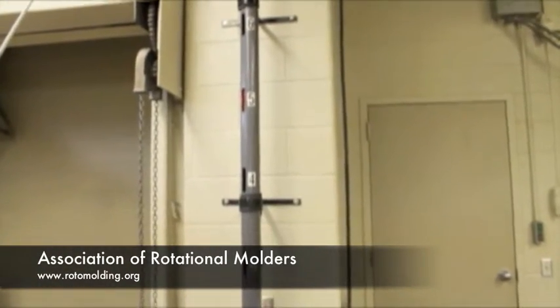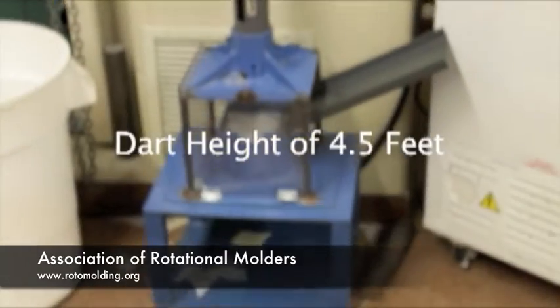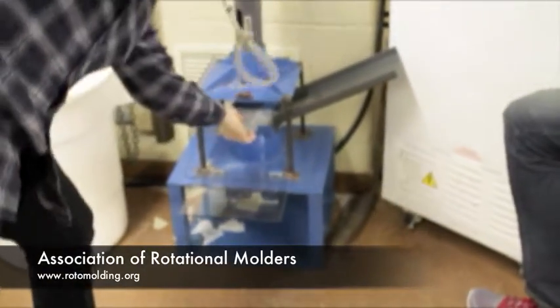If specimens pass, raise the dropping height by 6 inches and repeat test. Continue increasing the drop height by the same increment until failure occurs.